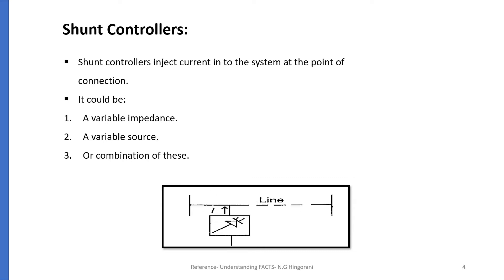Shunt Controllers are used to inject current into the system at the point of connection. The shunt controller could be a variable impedance, variable source, or a combination of these. Injection of current into the line is represented by a variable shunt impedance connected to line voltage as it causes a variable current flow. Shunt controller consumes or supplies variable reactive power when the injected current is in phase quadrature with the line voltage. Any other phase relationship will involve handling of real power as well.